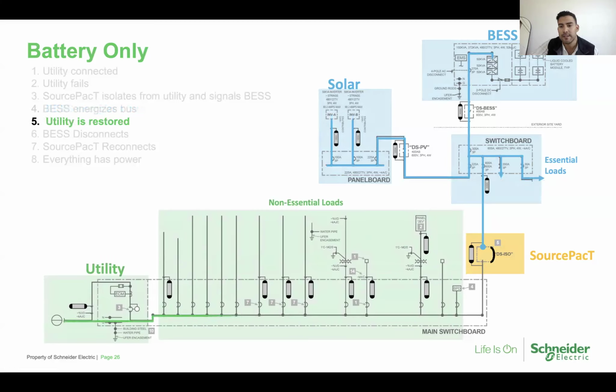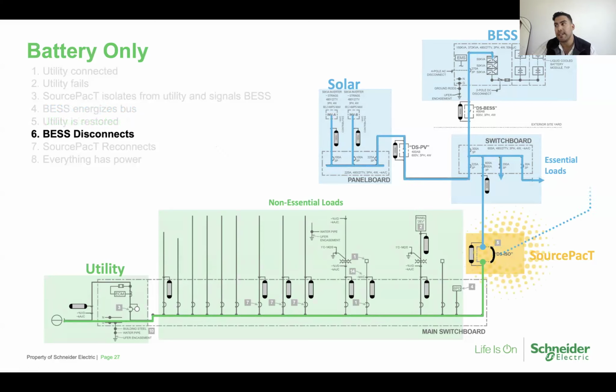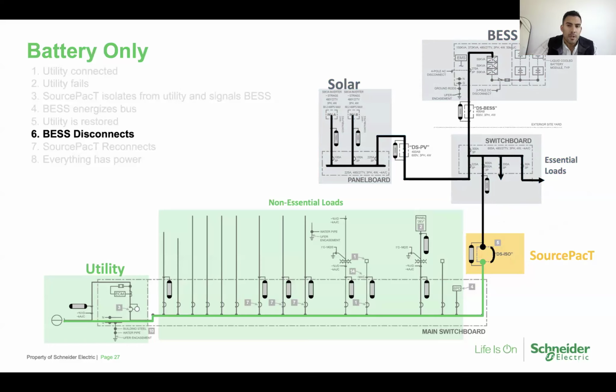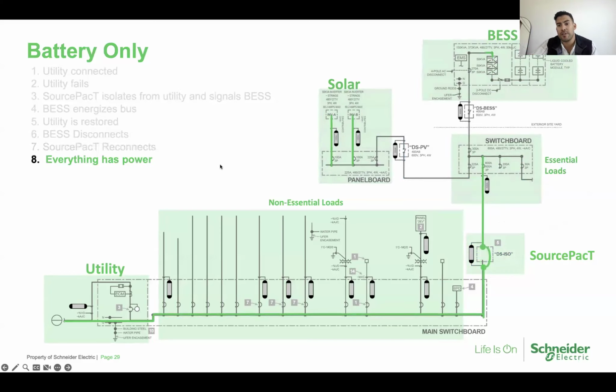Now, when utility is restored, SourcePacT will detect that utility is available on source 1. Once we detect that utility is restored, there'll be a time delay. SourcePacT will send a shutdown signal to the energy storage system, telling them that, hey, utility's been restored, shut down. That battery energy storage, those inverters will now shut down. At the same time, your solar system will also go dark. All those loads in the essential switchboard will lose power. SourcePacT will now reclose that breaker, so that breaker now will energize the upstream switchboards, and then once again, your battery energy storage system and solar system will sense that there's an available primary or anchor resource and synchronize once again in that grid interactive or grid tied mode.